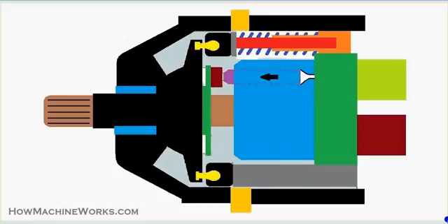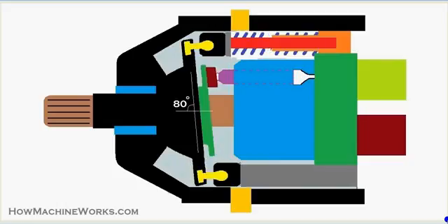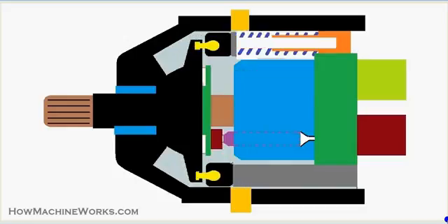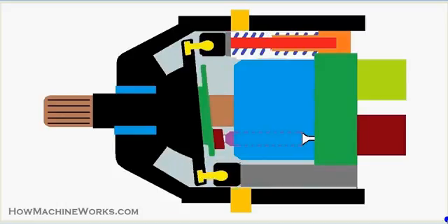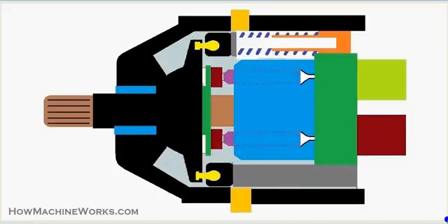And have a look at the piston. See the arrow mark. The piston is actually moving back, and that's the reciprocating motion happening. As a result of that, a suction happens at the top. You can see at the top the suction happening over there, and the bottom piston you can see is actually moving towards the front because the swash plate is pushing it towards the front, so there will be a discharge. So as this particular cylinder block is rotating continuously, the pistons at the top end will create a suction and the pistons at the bottom end will create a discharge.